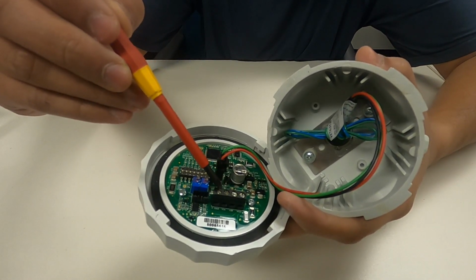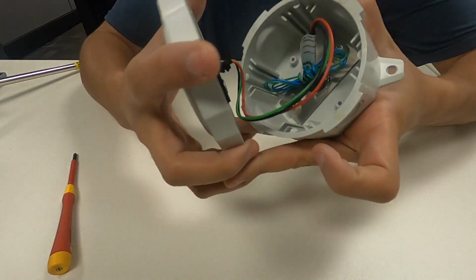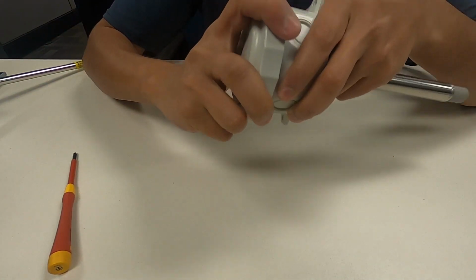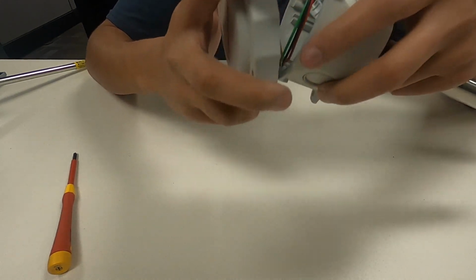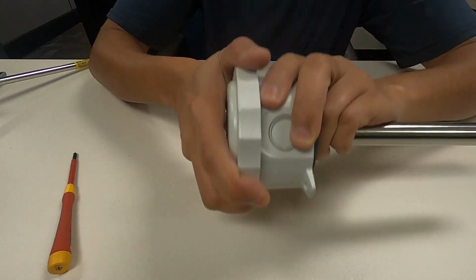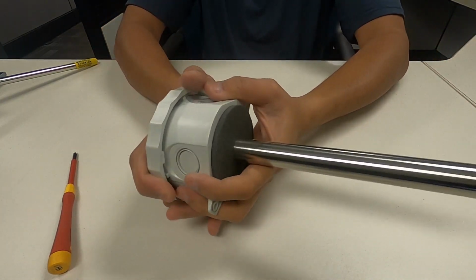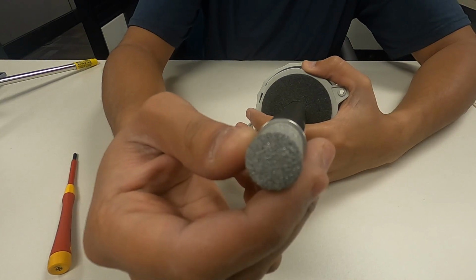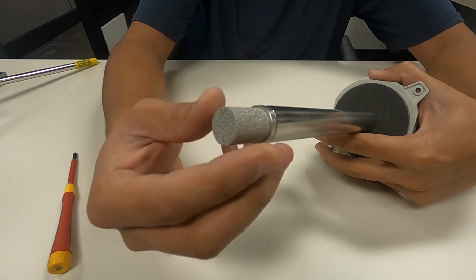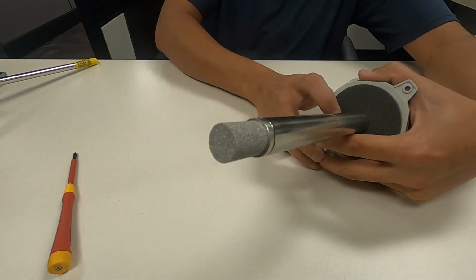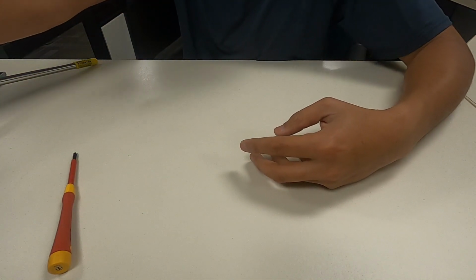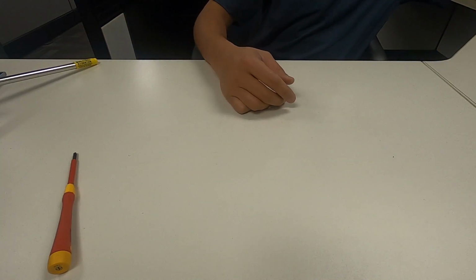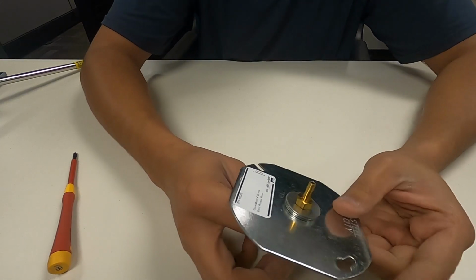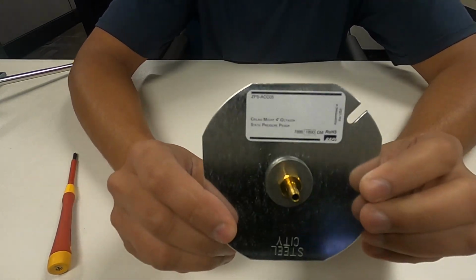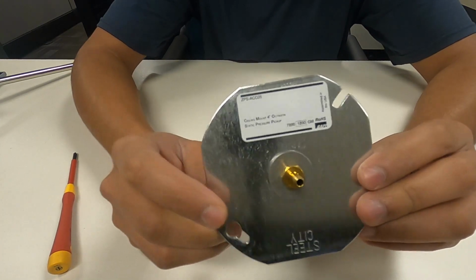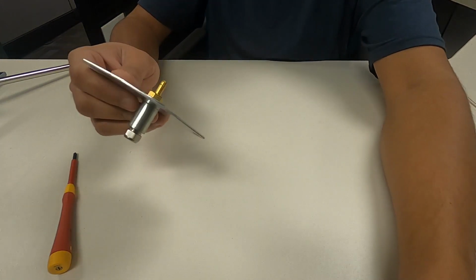The sensors will be recording the static duct pressure if they are mounted in a duct. The sensors can record the differential pressure between two rooms. The sensors can record the overall building pressure with respect to the atmosphere. In some cases, the duct static pressure will be used to measure the flow through the duct. I'm not saying this is the appropriate way to use it, but it can be used. And this is how I've seen it in my retrofit jobs.